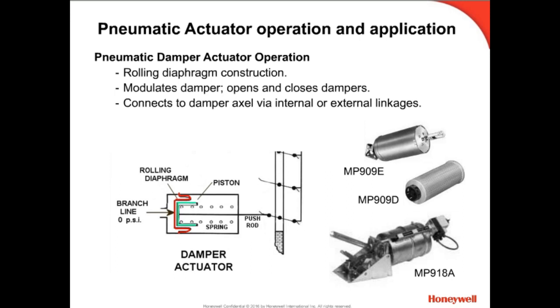The push rod is attached to the damper drive blades via a linkage assembly. The damper motor may be mounted internally or externally to the duct, and the linkage will involve push rods, pivot arms, and ball joints to meet mounting and movement requirements.